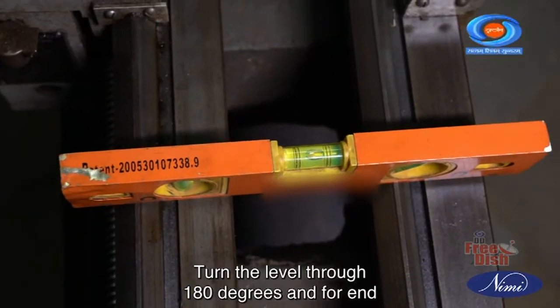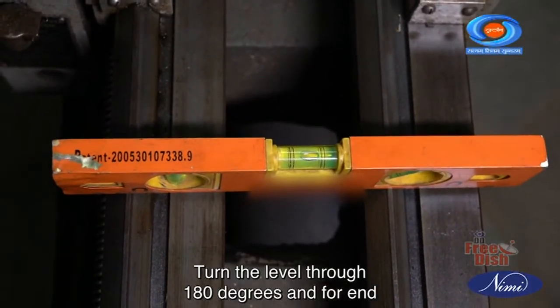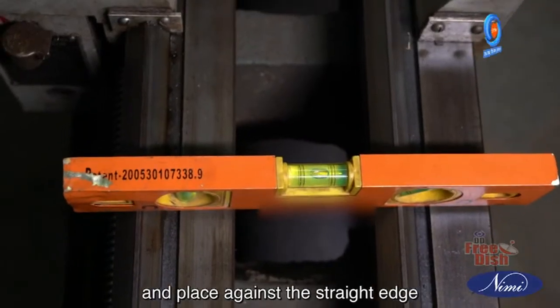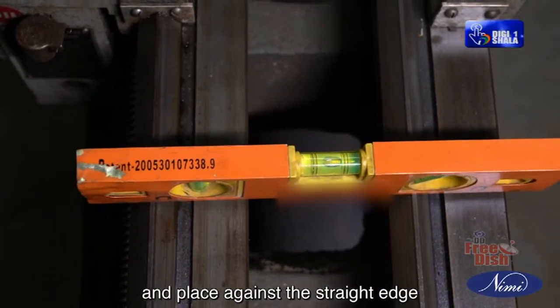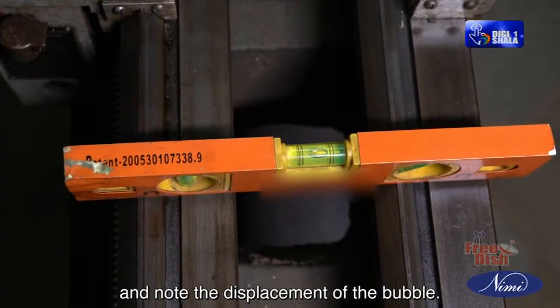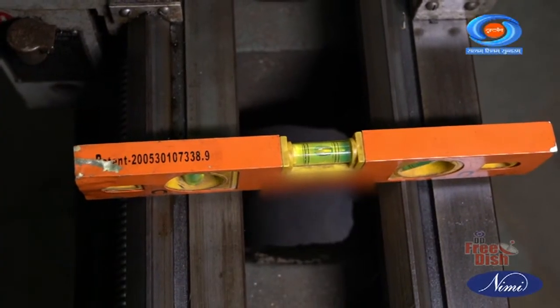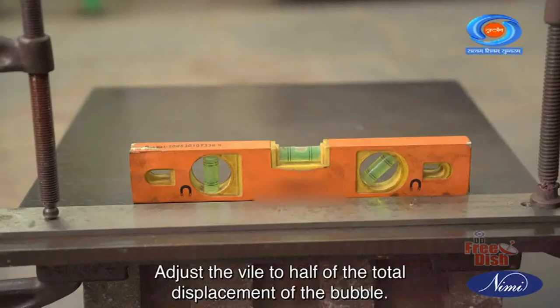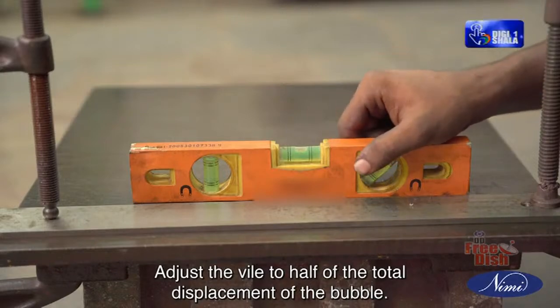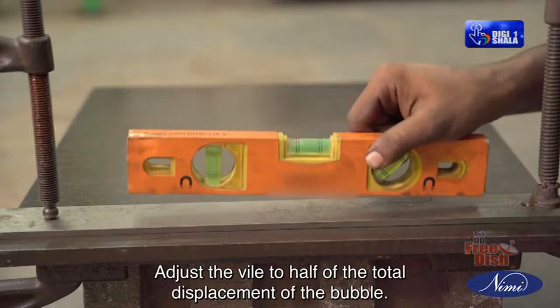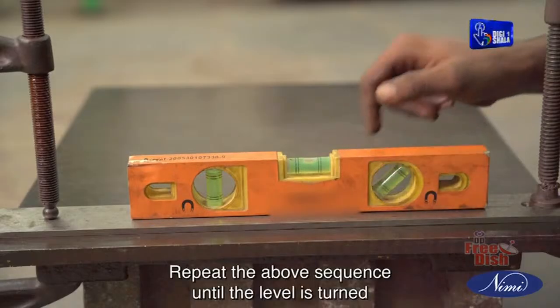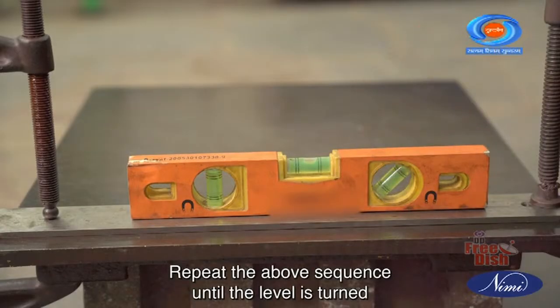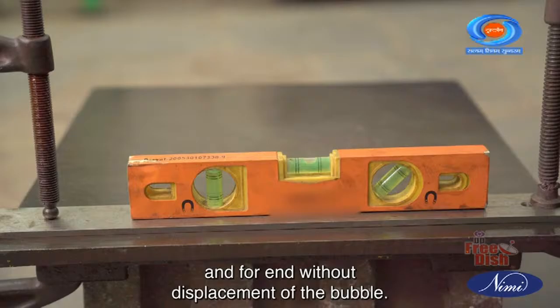Turn the level through 180 degrees end for end and place it against the straight edge and note the displacement of the bubble. Adjust the screw to half of the total displacement of the bubble. Repeat the above sequence until the level is turned end for end without displacement of the bubble.